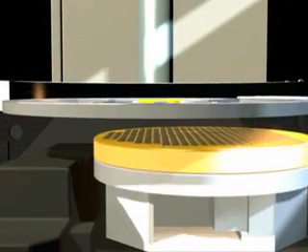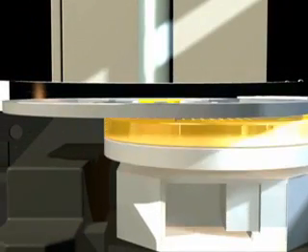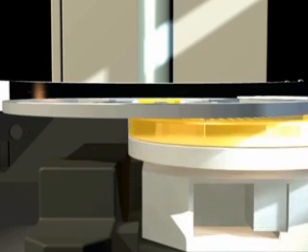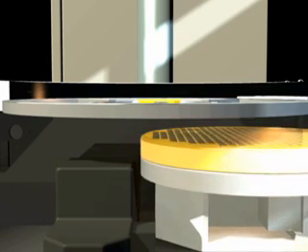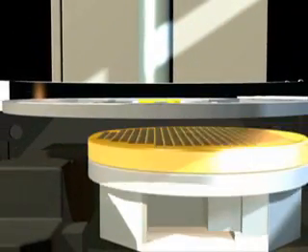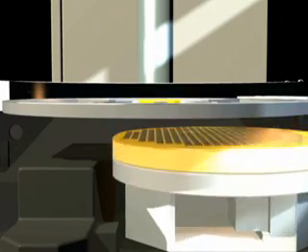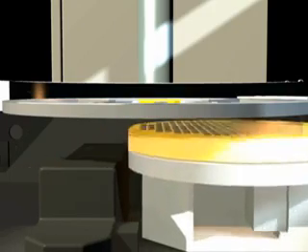The prober must be able to quickly adapt to the specific test needs of each type of product, including temperatures ranging from minus 60 degrees to over 200 degrees Celsius. It must also be able to push the wafer against the probe card needles with forces up to 200 kilograms, all while maintaining critical accuracy in both horizontal and vertical dimensions.